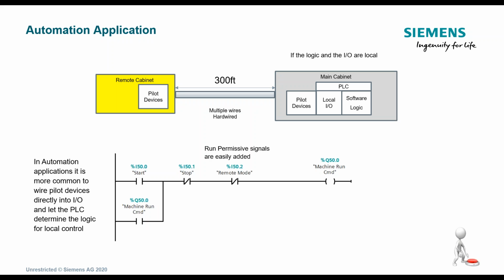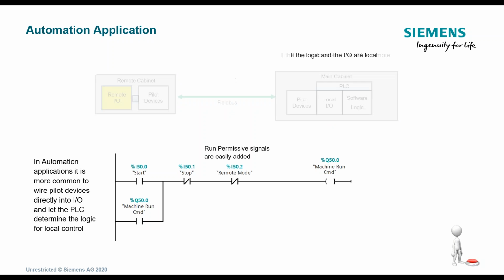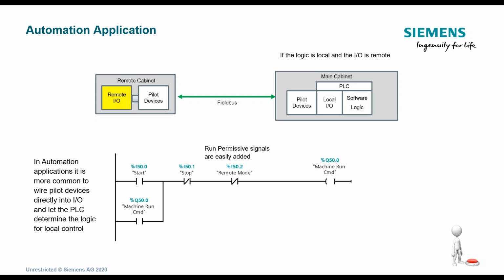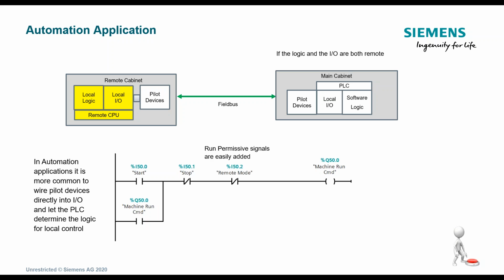Okay, so we're looking here as if we have a remote cabinet. We have the main cabinet with the PLC, pilot devices, maybe an HMI, and then maybe 300 feet away we've got the pilot devices for a remote cabinet and so forth. And then we have a field bus where we're communicating from that remote cabinet. And you might put logic in that cabinet too.